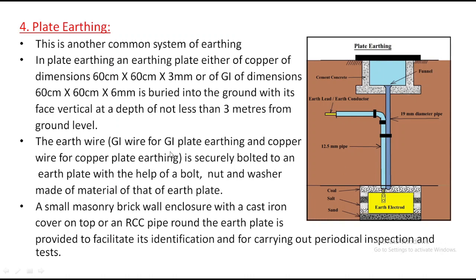The earth wire is a GI wire for GI plate earthing, and a copper wire for copper plate earthing. You can use this plate, copper or GI, anything. It is securely bolted to the earth plate with the help of a bolt. So look here, this is the GI wire. If it is GI, we take the GI plate and it is bolted. By using the bolts we can attach this, with a nut and washer made of the same material as the earth plate.